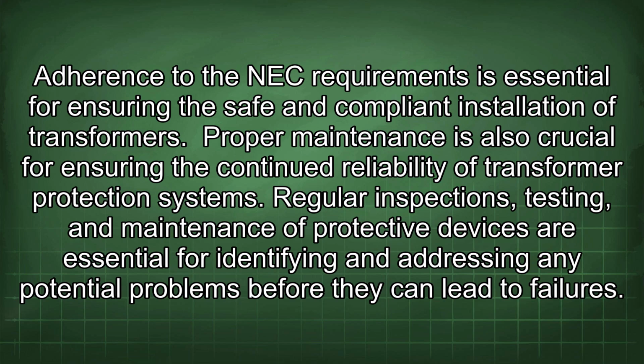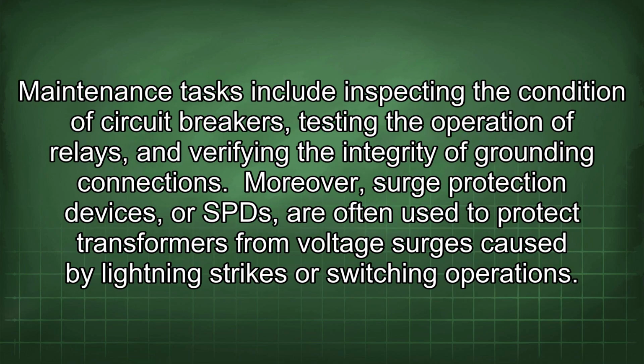Proper maintenance is also crucial for ensuring the continued reliability of transformer protection systems. Regular inspections, testing, and maintenance of protective devices are essential for identifying and addressing any potential problems before they can lead to failures. Maintenance tasks include inspecting the condition of circuit breakers, testing the operation of relays, and verifying the integrity of grounding connections. Moreover, surge protection devices, or SPDs, are often used to protect transformers from voltage surges caused by lightning strikes or switching operations.